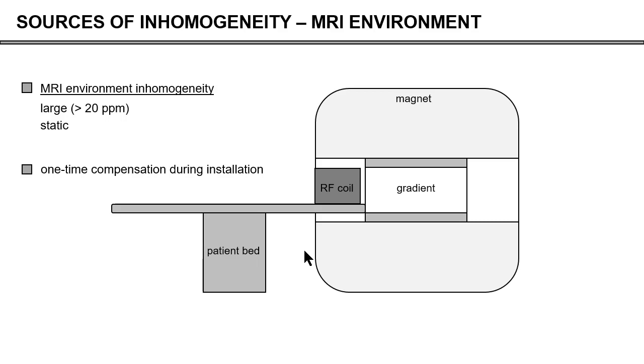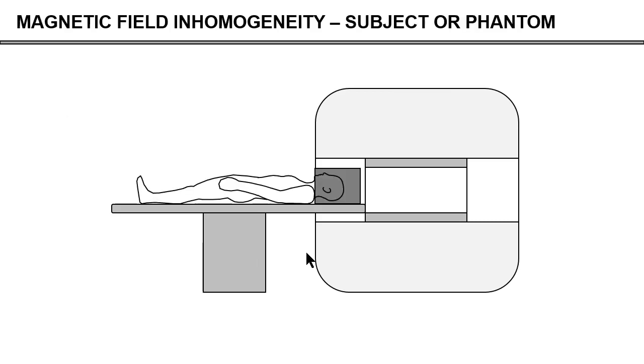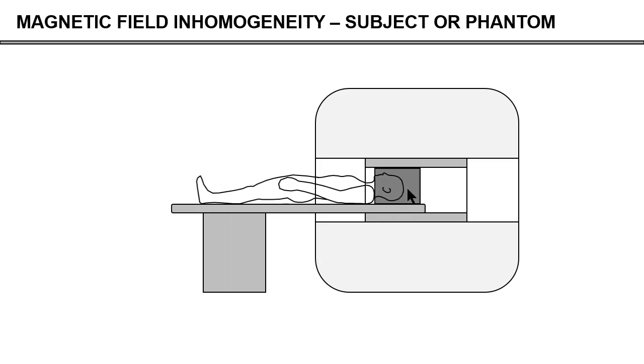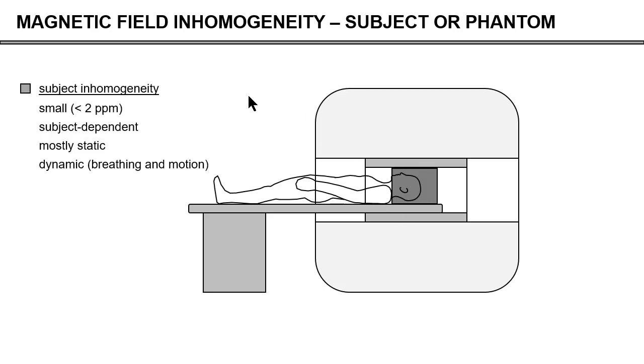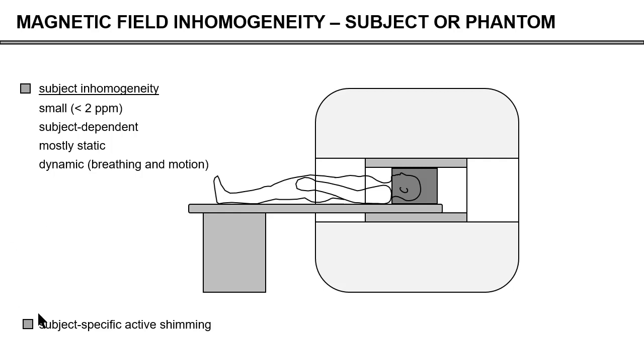The problem that we as researchers deal with are mostly related to the sample that we put in — either a phantom or a human or an animal. Every human is slightly different, and so the inhomogeneity that the sample introduces will vary from human to human or from phantom to phantom. So the inhomogeneity that your sample introduces is relatively small, but it is subject-dependent, and therefore you need to deal with it every time you put a new subject in. It is mostly static, and there are some dynamic components related to breathing and motion. This kind of inhomogeneity requires subject-specific active shimming, and that will be the bulk of my talk today.